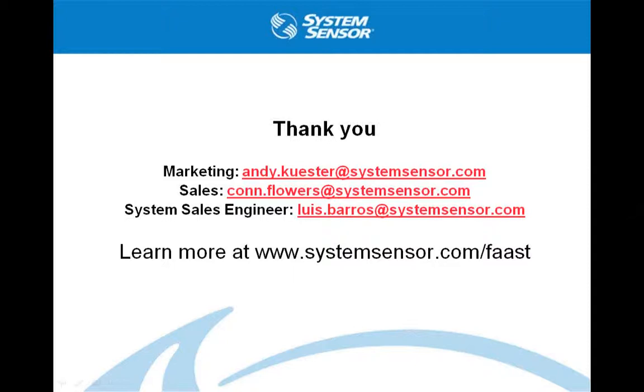If you go into the technical support section of our System Sensor website, we have this technical paper which basically gives you a line-by-line how-to of how to set up an aspiration system within a duct system. I recognize that even though a duct smoke detector works extremely well, some applications don't allow for that space on the exterior of the duct to mount it. Aspiration systems are great for that because you can mount the actual device further away from the duct and just run the pipe into an area where you can access and tap into the ductwork. So definitely a great application and far more widely used and accepted than I had thought previously.